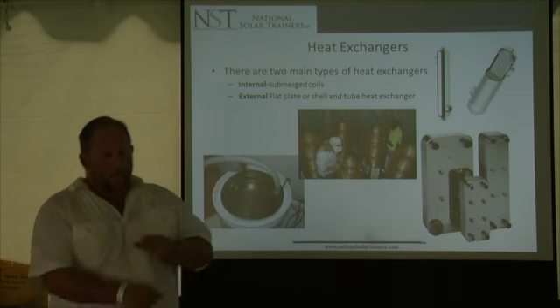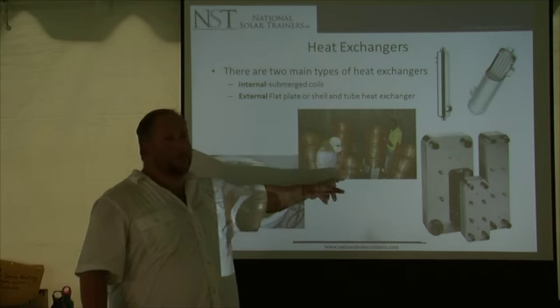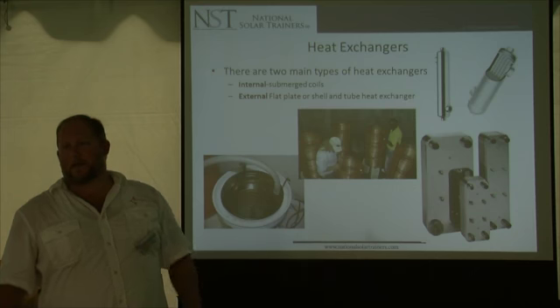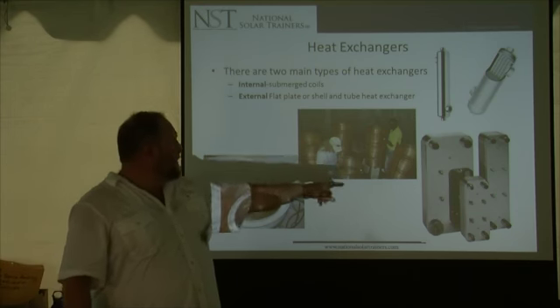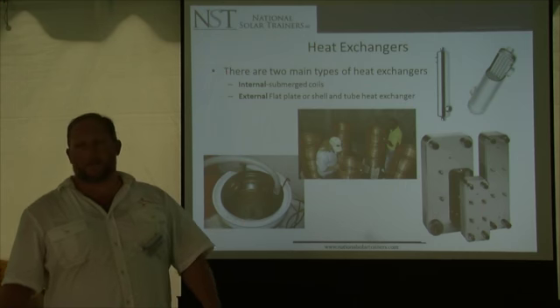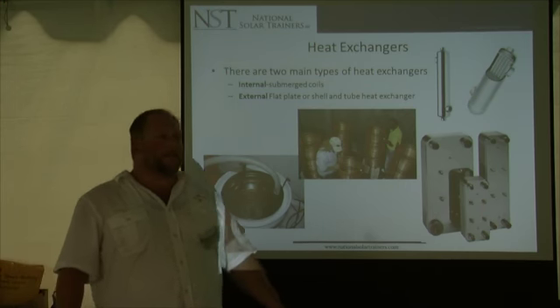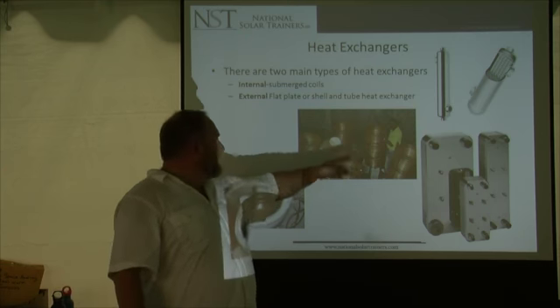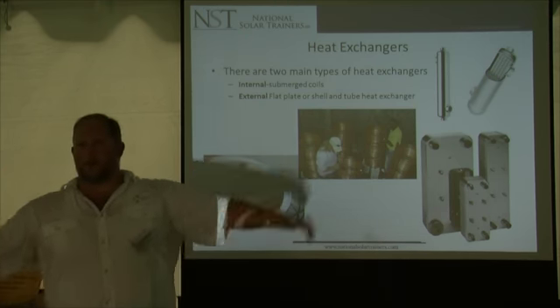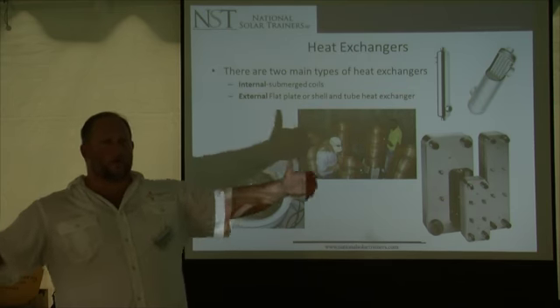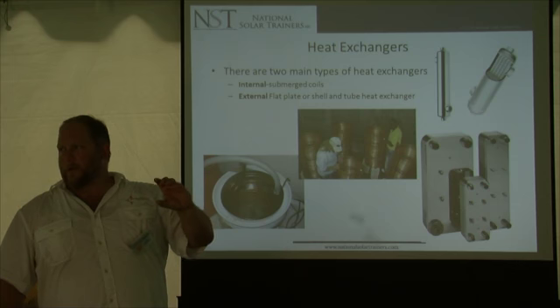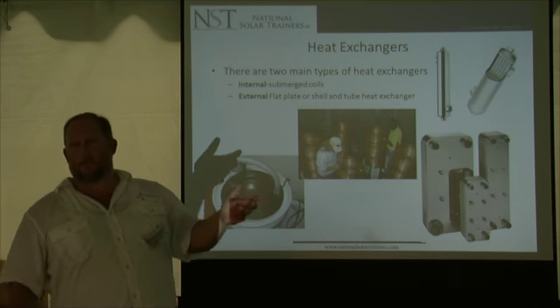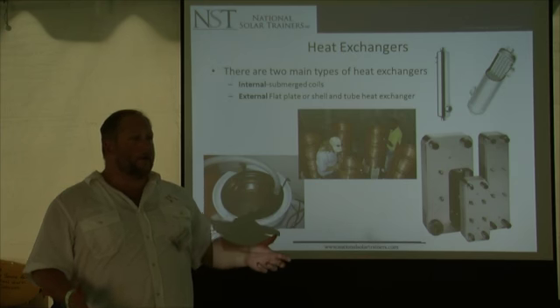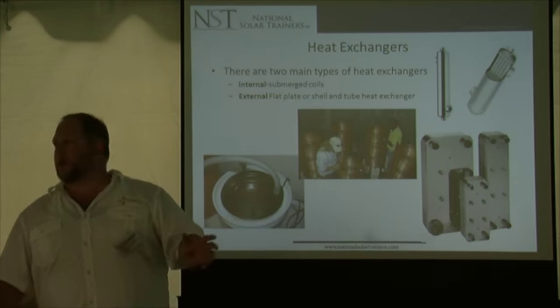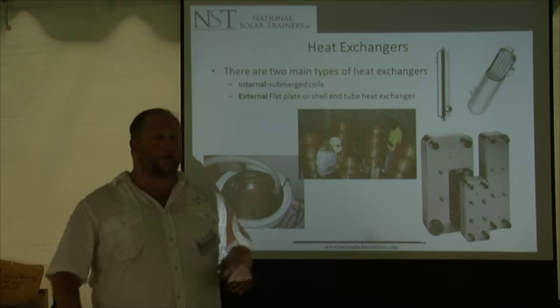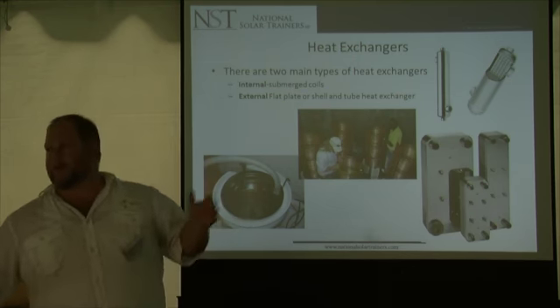Right? This is a storage tank. These gentlemen are down in the Bahamas. This is a 4,000 gallon storage tank with these copper coils, and they're all tied into their domestic hot water system. Now they got about 60 gallons a minute. And you think, well, why are we using 60 gallons a minute on those 3/4 inch coils? Why don't you use 1.5 coil? Why don't you use bigger coils, wider coils? And even so, the answer is it's surface area to volume ratio. So a 3/4 inch coil is always the best coil, no matter what your application is. The question is, how long does that coil have to be?